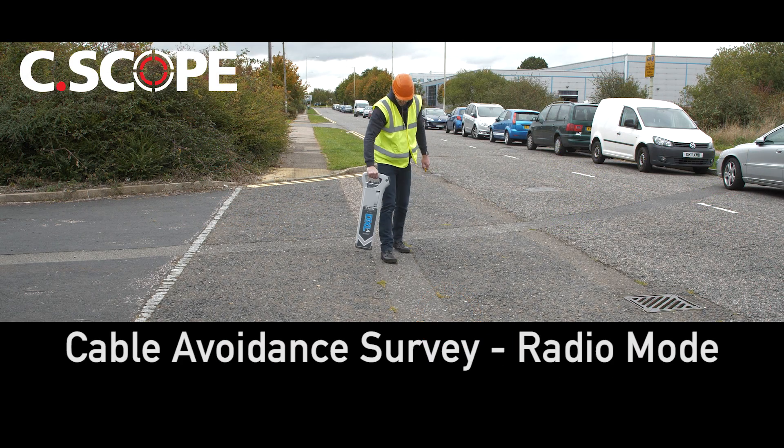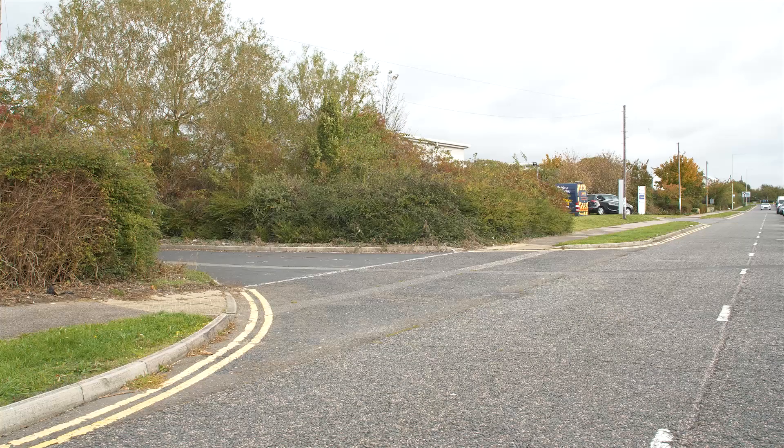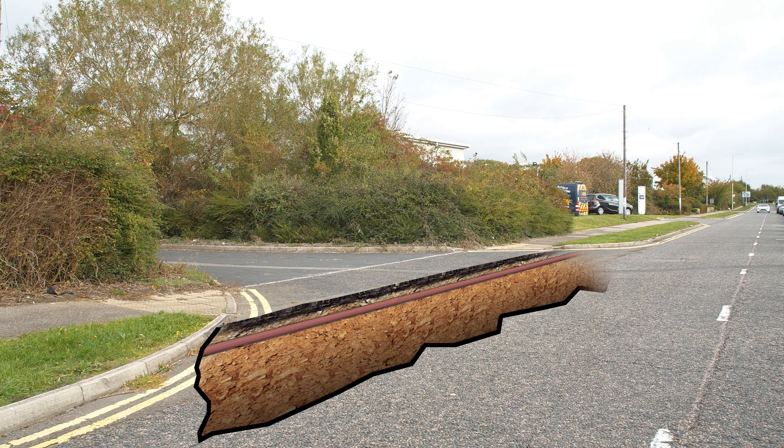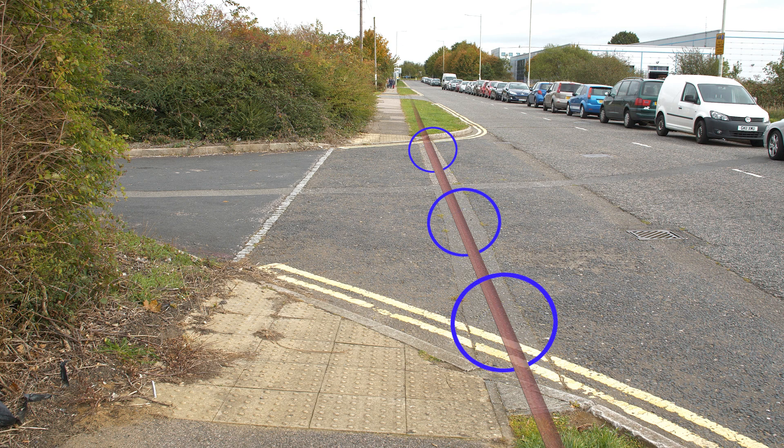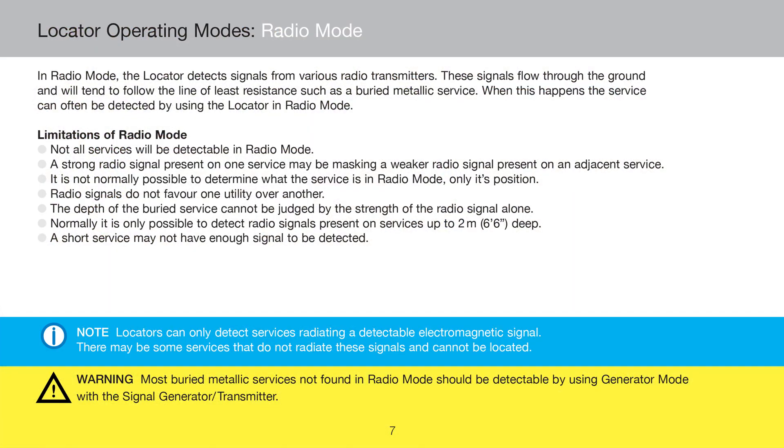Theory of the radio mode. When used in radio mode, C.Scope cable avoidance tools detect re-radiated radio type signals originating from various RF frequency transmitters that flow through the ground and tend to follow the line of least resistance such as a buried metallic pipe or cable. Not all pipes and cables will be detectable in radio mode and it is not always possible to determine the exact identity of the metal pipe or cable from the radio signal alone. Please refer to the locator's instruction manual for further information on the limitations of the radio mode.